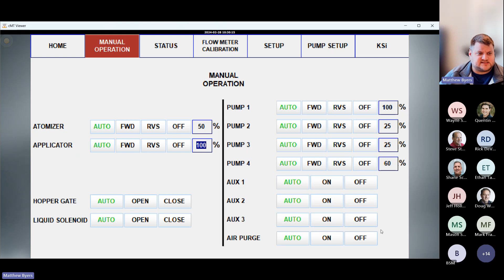Pumps — when you're cleaning your pumps out, same thing here. You can run those in forward, you can reverse those as well, and then there's the speed at which they're going to run. You can run your auxiliary device manually, set through here, and then the air purge that fires after every batch — if you want to run that and test it, it's set right there.